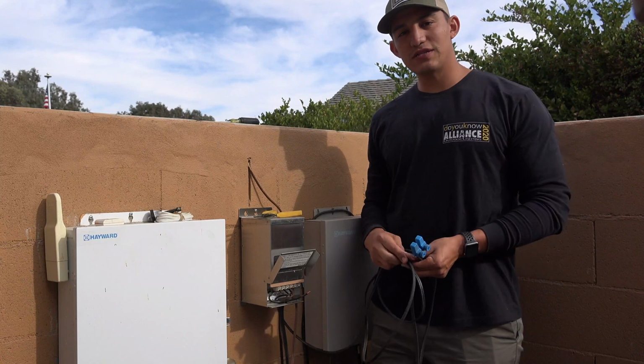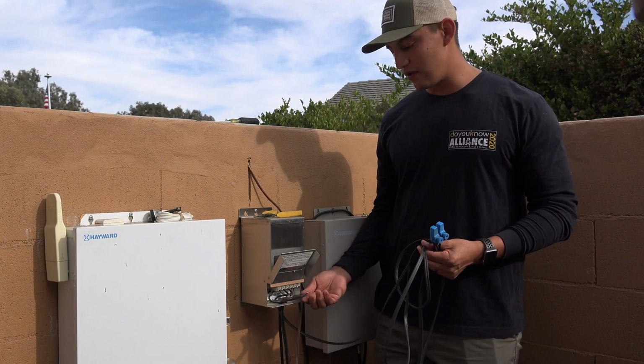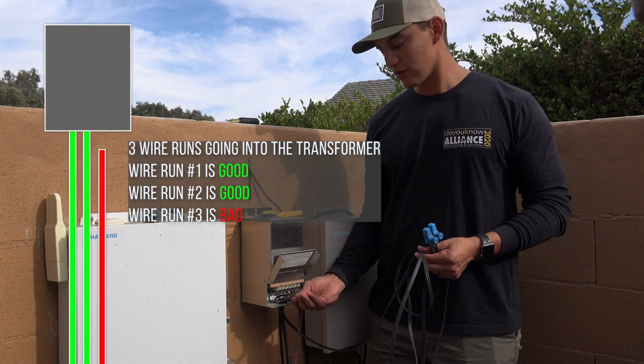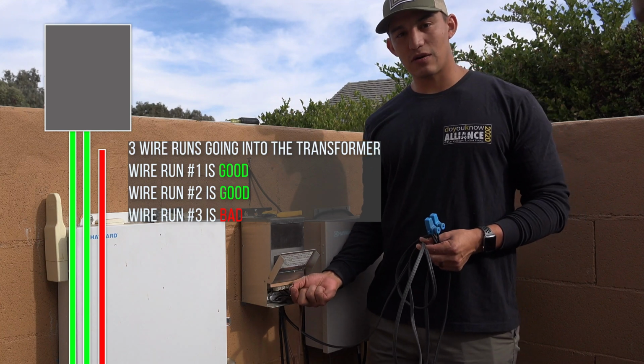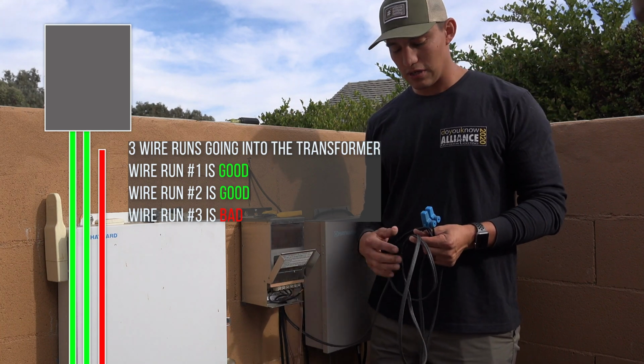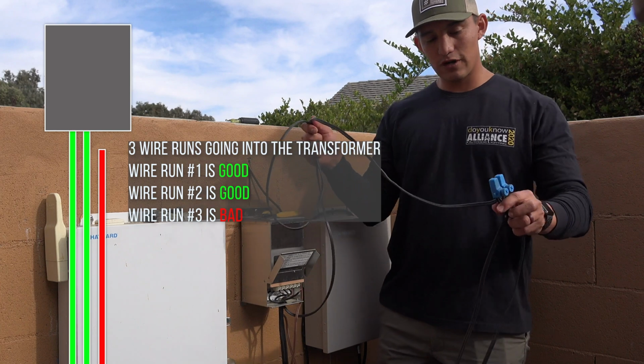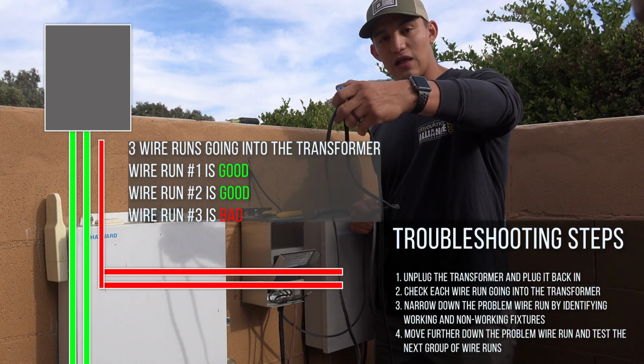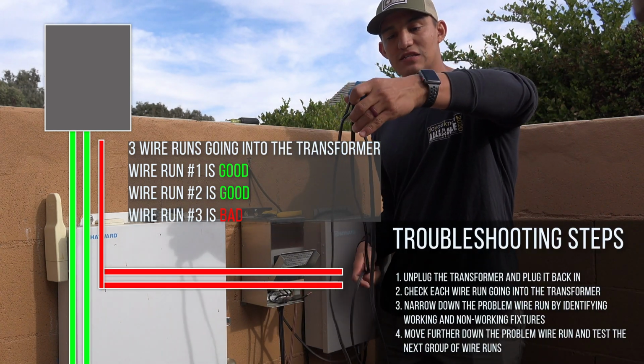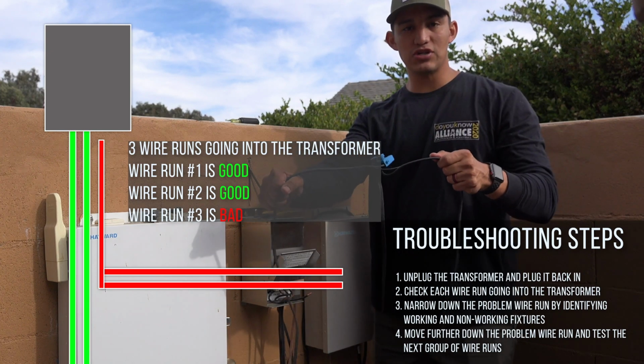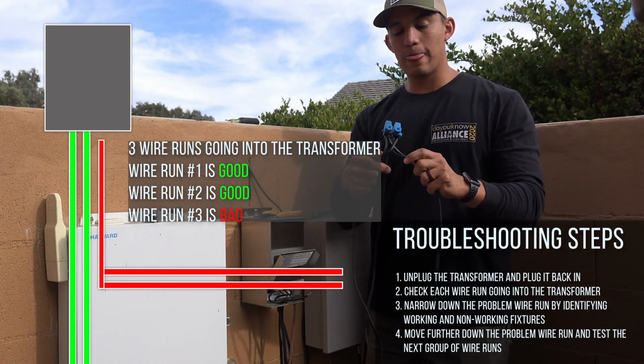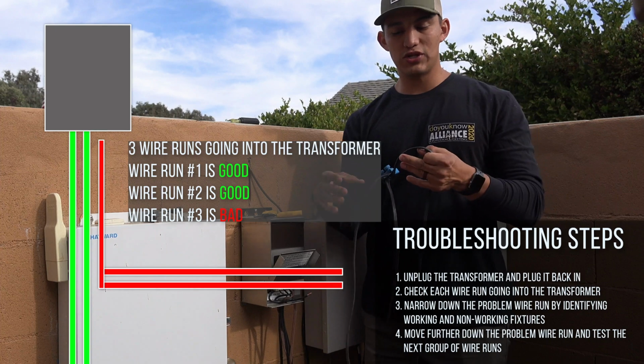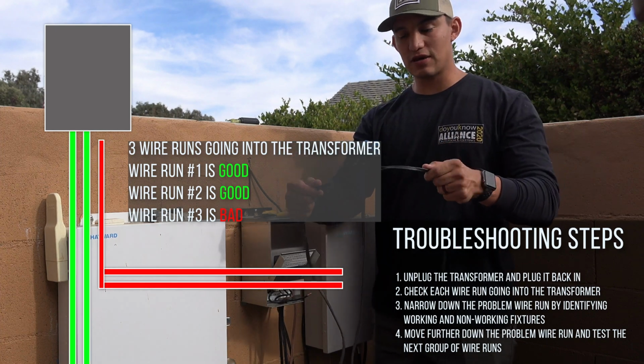All right guys, so we've run into somewhat of a common situation here that many of you might come across in the field. Lead number three is giving us our problems, causing our short. So here's our lead coming out of the transformer, and then at some point down the line or at your job site, it's going to split and go two different directions. Now we've got to figure out which direction or which split is causing the real issue.